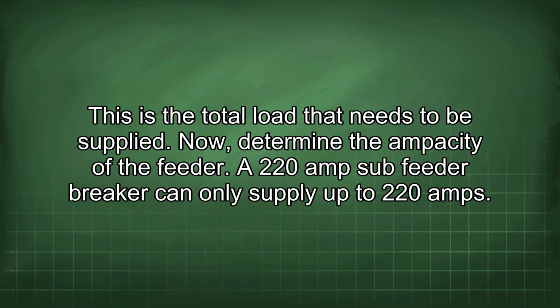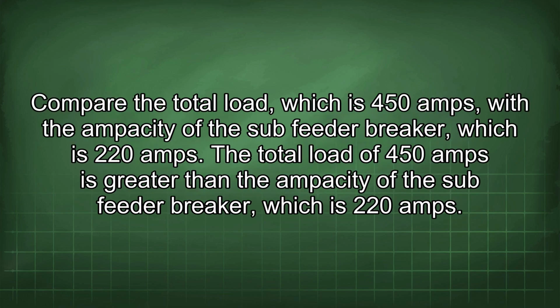Now determine the ampacity of the feeder. A 220 amp subfeeder breaker can only supply up to 220 amps. Compare the total load, which is 450 amps, with the ampacity of the subfeeder breaker, which is 220 amps. The total load of 450 amps is greater than the ampacity of the subfeeder breaker, which is 220 amps.